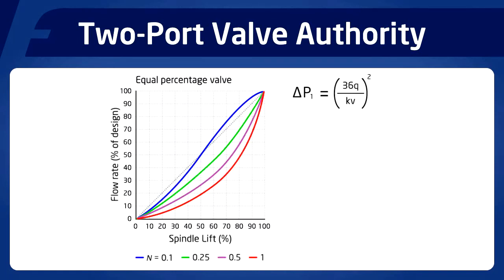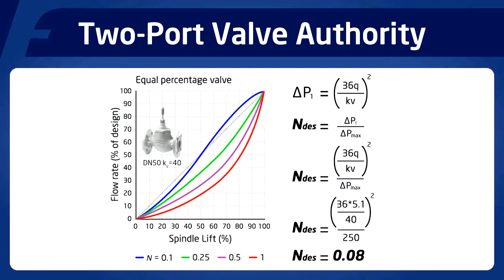Whilst we know the authority of the pressure independent control valve will be 1, we can use the data collected and the kV of the DN50 valve to calculate the authority. As we can see, the authority of the conventional two-port modulating valve is less than 0.1, and explains why the valve has to close 90% to absorb the pressure, and explains the frequency and the amplitude of the flow variation as the valve hunts for position to control a stable flow and temperature.